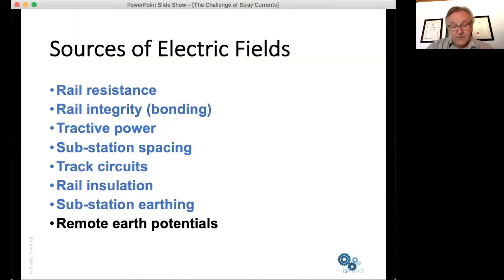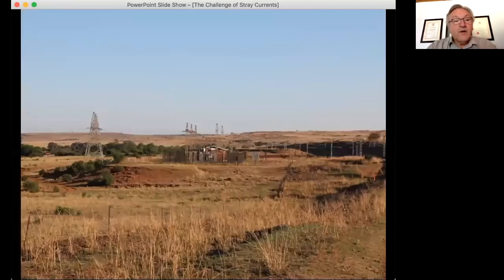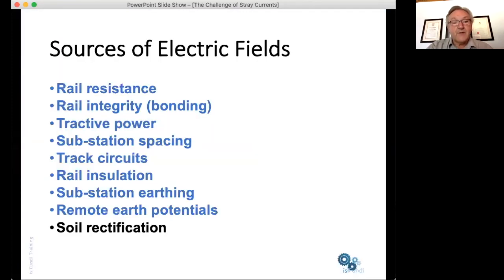Traction substations may be located many kilometers apart and are fed through overhead power lines, shown here. We've seen situations where the potential with respect to remote earth of two adjacent traction substations differs by as much as 200 volts, even though each is nominally at ground potential. This plays havoc with signaling systems, not to mention stray currents affecting pipelines.